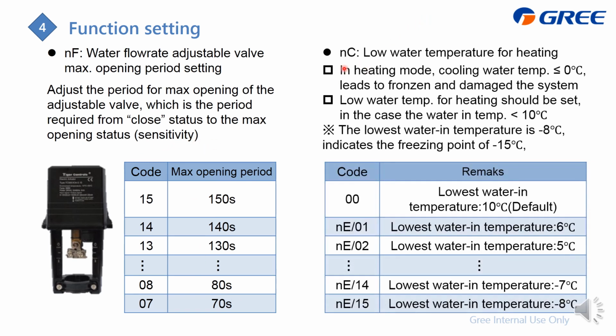Next is NC, which is the low water temperature for heating. And as you know, in heating mode, we just cool down the water, right? And then if the water is lower than the freezing point, it results in the water system freezing, which may damage the system, right? And also from the operating range for heating, our lower limit of the water in is 10 degrees.